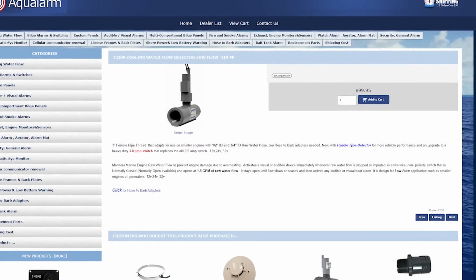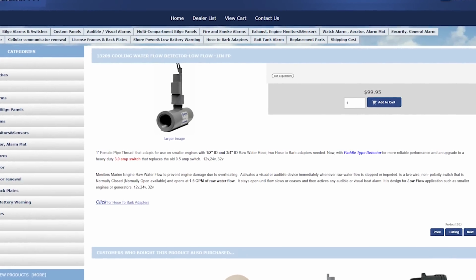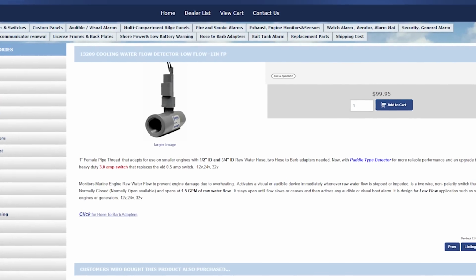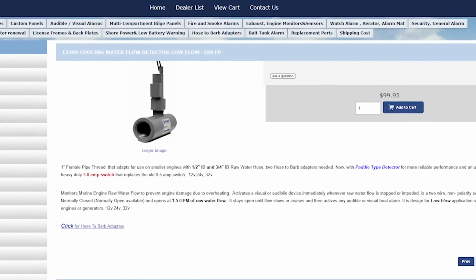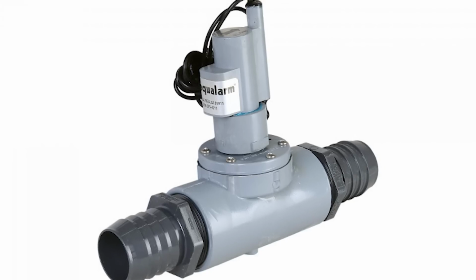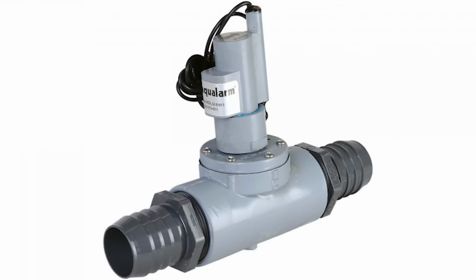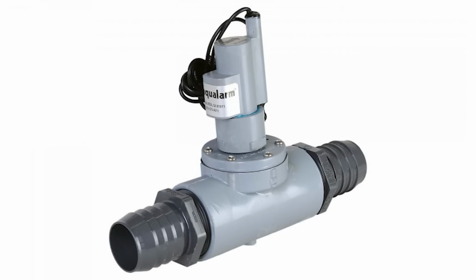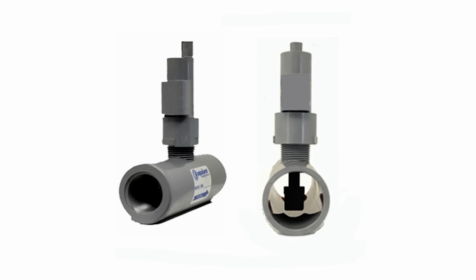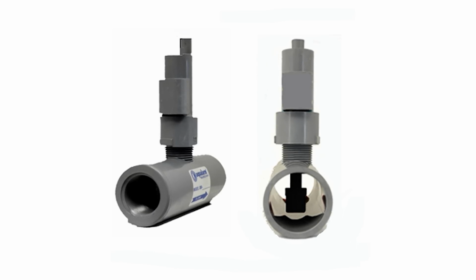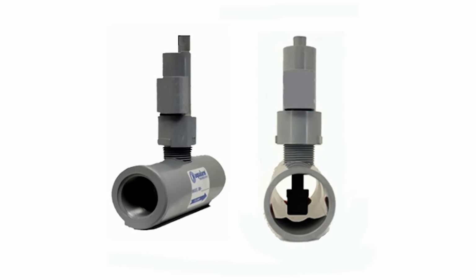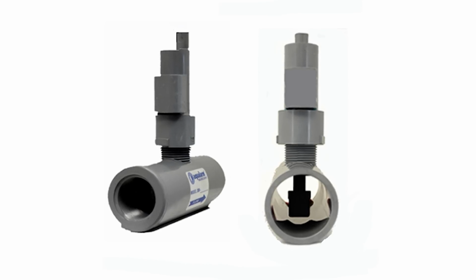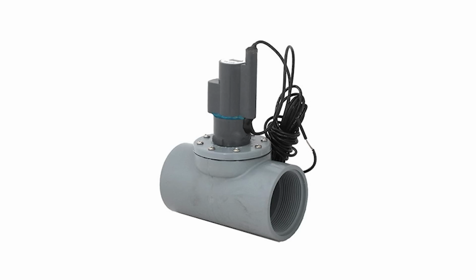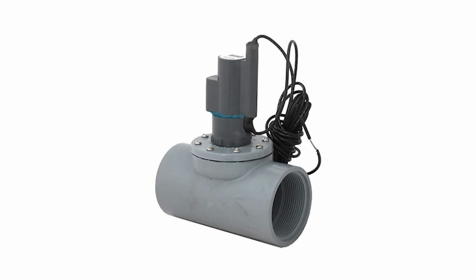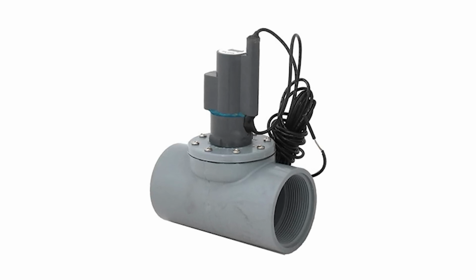The product description says: 1-inch female pipe thread that adapts for use on smaller engines with 1/2-inch ID and 3/4-inch ID raw water hose; two hose-to-barb adapters are needed. It's a paddle-type detector that monitors marine engine raw water flow to prevent engine damage due to overheating. It activates a visual or audible device immediately whenever raw water flow is stopped or impeded. It's a 2-wire, non-polarity switch that is normally closed. They also have a normally open version available, which opens at 1.5 gallons per minute of raw water flow, and stays open until water flow slows or ceases, then activates any audible or visual boat alarm. It's designed for low flow applications such as smaller engines or generators, and runs on 12, 24, or 32 volt.